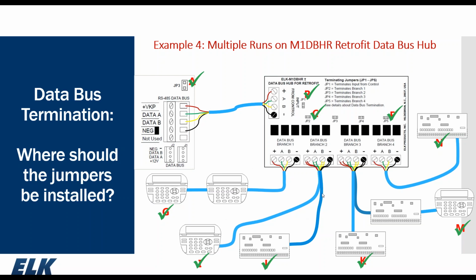Branch 2, 2 home runs. The last device on each home run would be terminated. In this case, the branch is in the middle, so it would not have a terminating jumper. Branch 3 follows that same scenario, the last device on each home run, but not the branch. And then finally, branch 4 is a single device, so it's terminated as well as the branch itself, JP5 here. Power down, measure across A and B. We should read between that 60 and 70 ohms across each one.